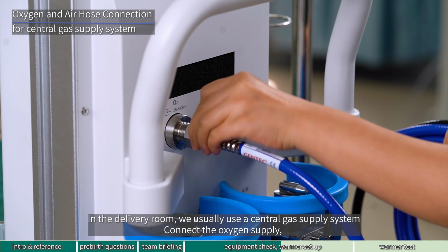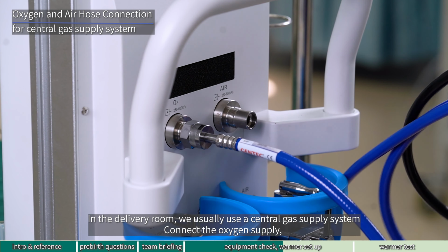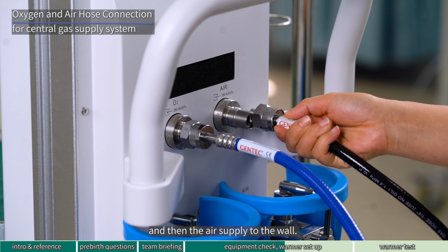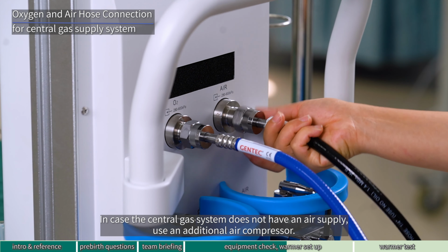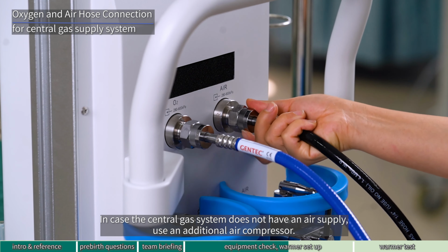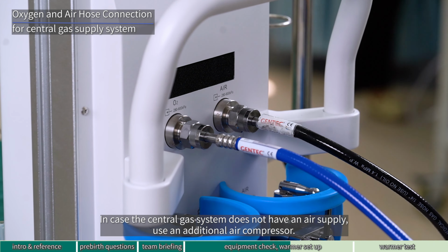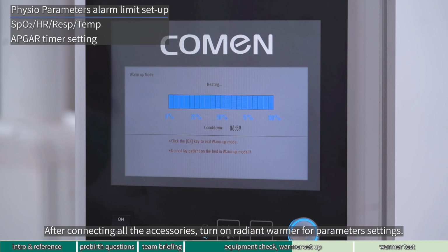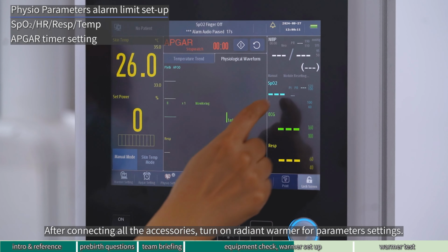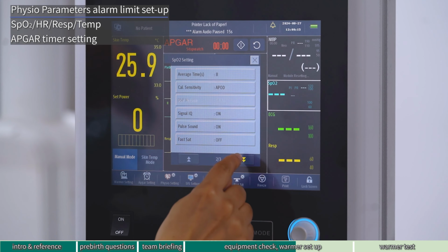In the delivery room, we usually use a central gas supply system. Connect the oxygen supply and then the air supply to the wall. In case the central gas system does not have an air supply, use an additional air compressor. After connecting all the accessories, turn on radiant warmer for parameters settings.